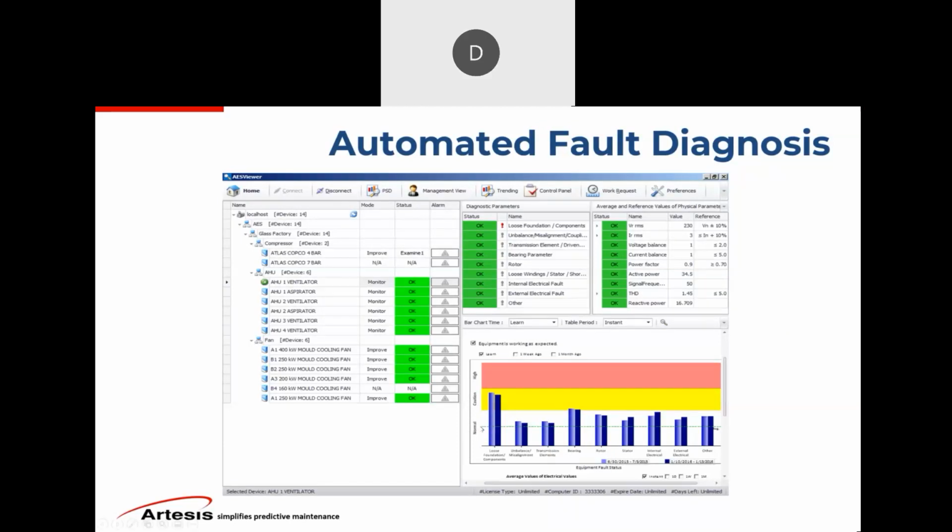But we want to know, where did we start when we first started monitoring, and where are we currently? If I look at this stator, the internal electrical, maybe there's some insulation degradation going on there. So it's starting to climb up. We're still in the white, good area, but why? So occasionally it's good to look at these, even though everything's in monitor mode. There's nothing in alarm. But this caution, there's just a lot of information here, but it's simplified.